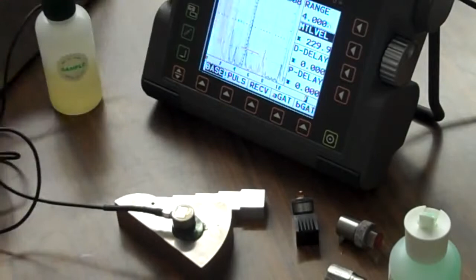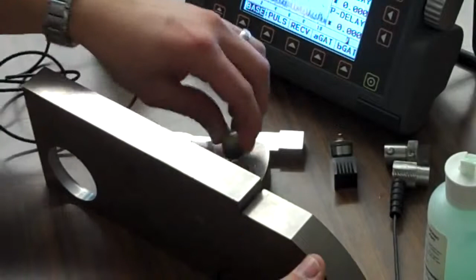So if we go to a 4-inch block - now I'm moving a bunch of stuff around here - if we go to a 4-inch block, slap a little coupling on it, we have a signal come right up at 4 inches because we represent 0 inches all the way out to 4 inches. Okay, there's the velocity of our material, and we're pretty close. And when we go to the 1-inch side again, there they come right back up: 25, 50, 75, 100. Good with that?